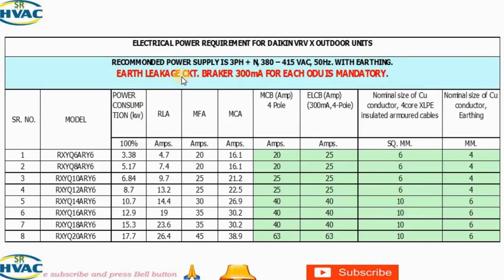Friends, this is the recommended power supply for Daikin VRV X outdoor unit. You can see there are different systems from 6 to 20. For RXYQ 6 ARY6, the power consumption will be 3.38. It might increase in 10, 12, 14. The power consumption, the load may be increased. You require 20 ampere for MCB, and the ELCB will be 25, and the cable size will be 4 or 6 square mm required for this 6 HP unit, and the minimum size of copper for conduit for earthing will be 4 mm. You need 4 mm earthing.